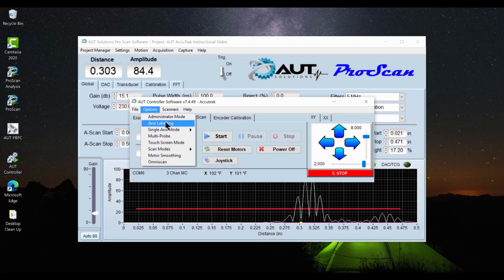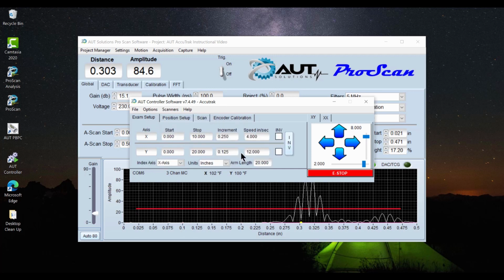The other options that we have here, if you're setting up for a B scan, you do have the ability to go into single axis mode and disable your Y. So you can move your Y into position of the center of the scanner. Simply click disable Y axis and you will actually go in and remove the exam setup Y, and it will simply drive forwards and backwards for you. A couple other things that we might want to go through. If you want to label your axes, you would simply do that here. And it looks like we're good to go.